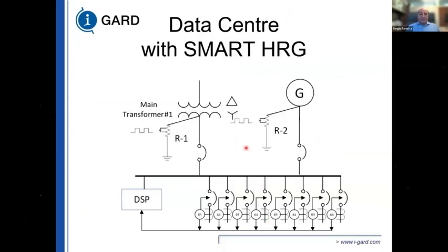So this is the way it looks in the same data center. Now we have 2 resistors and 1 high resistance grounded system on the actual distribution system. So we have a 0 sequence CT on each one of the breakers, and we can monitor which feeder has the fault. If you saw my example previously, we saw that the fault was on A phase on feeder number 3. So this would have feeder number 3. We start looking downstream from this point to find where the fault is. If a second fault occurs on a different phase or on a different feeder, these 2 feeder modules will communicate with each other, and the one that you program to be of a lower priority will trip first.